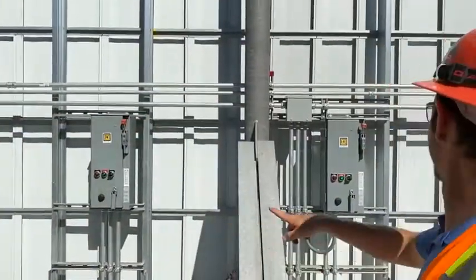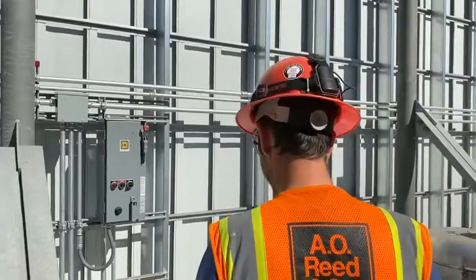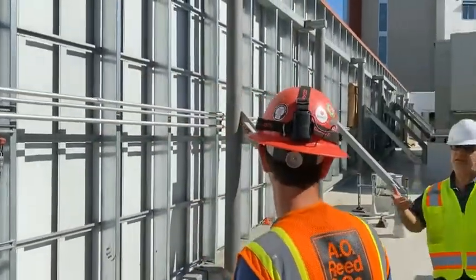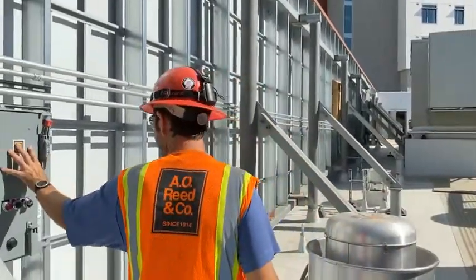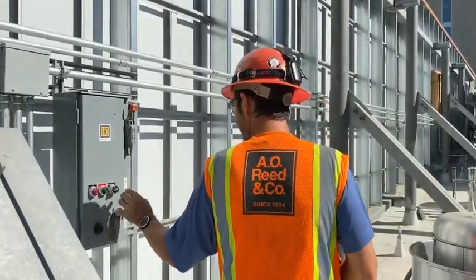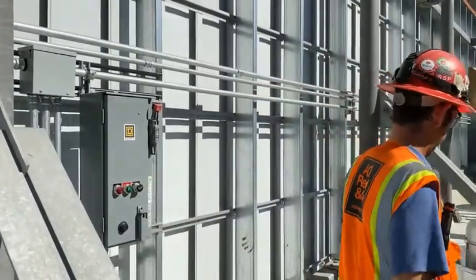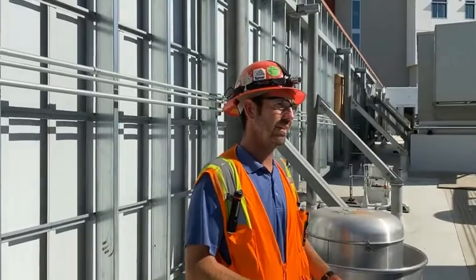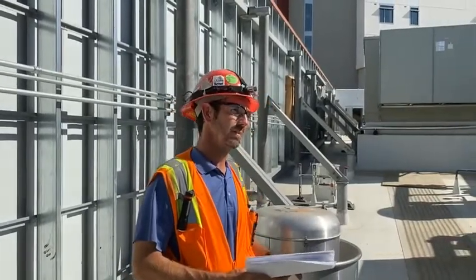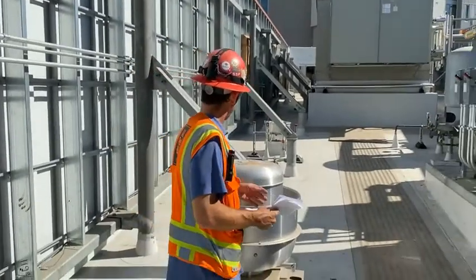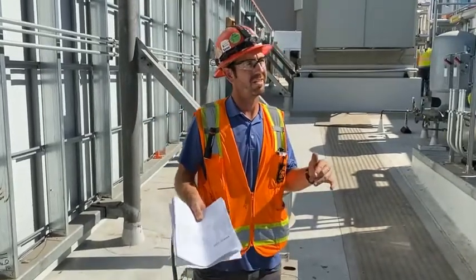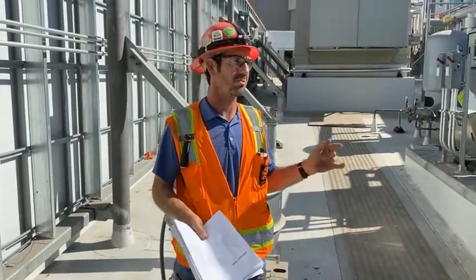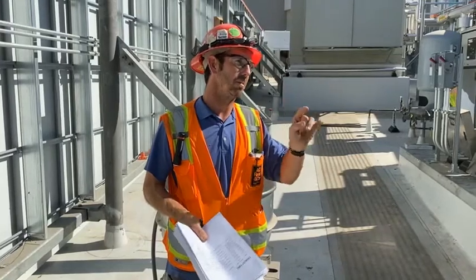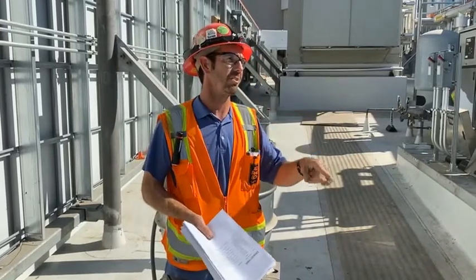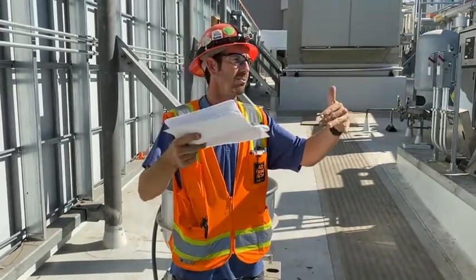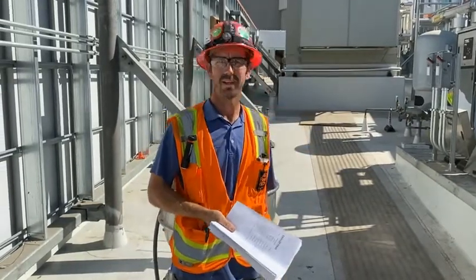This one was this room. Dishwashing exhaust fan, exactly. This is the starter for that unit. Same thing again. Switch will be in auto, off, doesn't matter. The Ansul system's turning it on and off. Some of these have push buttons downstairs though, so the electrician knows where those locations are. There'll either be a push button, and if somebody forgets to turn on the push button, there's still a temperature switch that can turn on the fan as well. Okay?